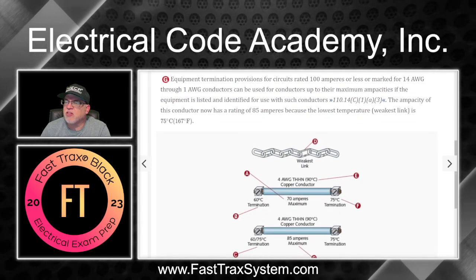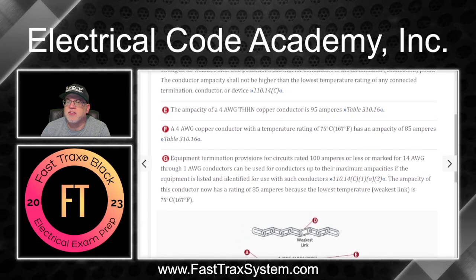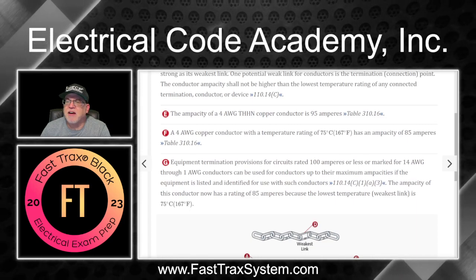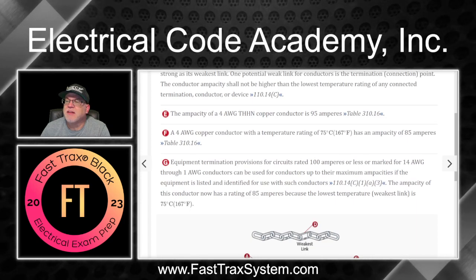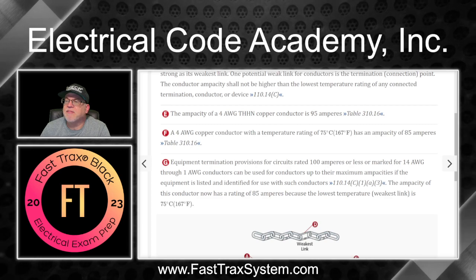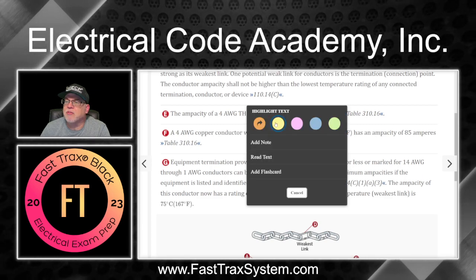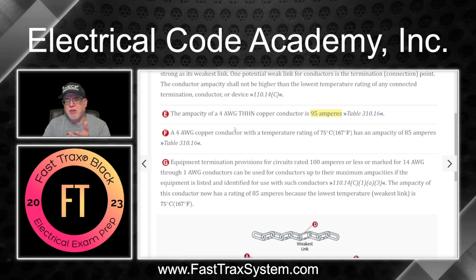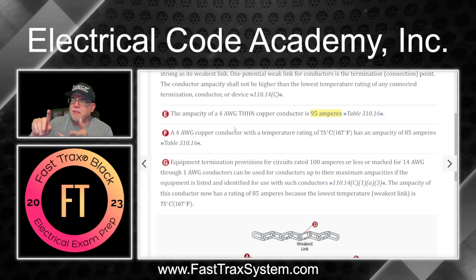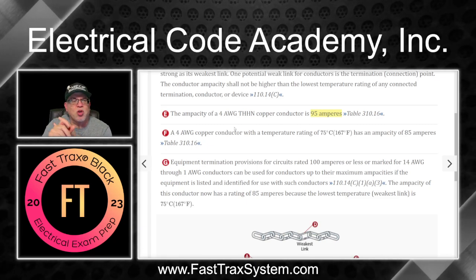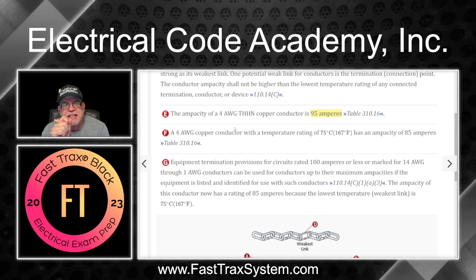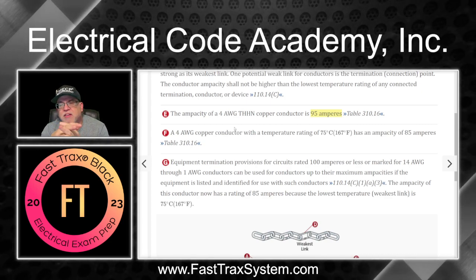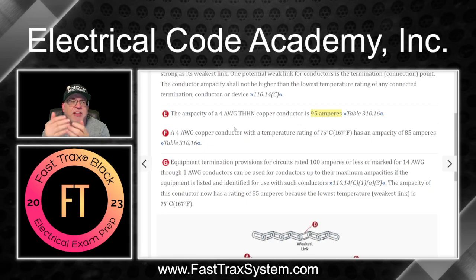Now, E is talking about the conductor, it seems. It says the ampacity of a 4 THHN copper conductor is 95 amps. Now, the first thing somebody will say to me is, wait a minute, we've been talking about 70, we've been talking about 85. How in the world do you get 95? Well, that's because that is the ampacity of the conductor.